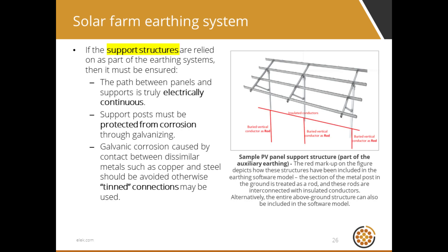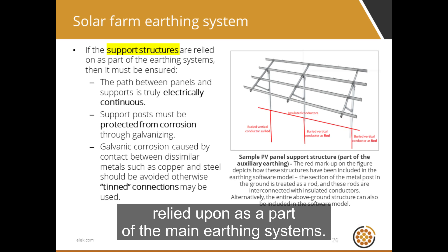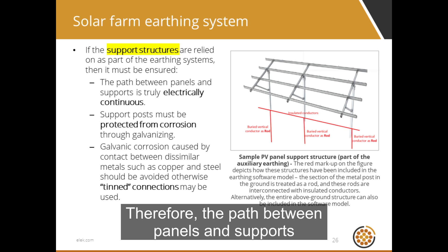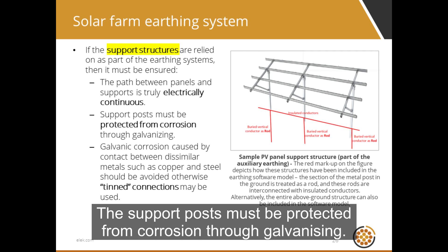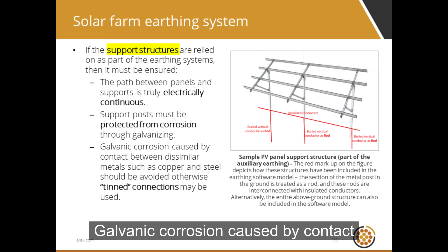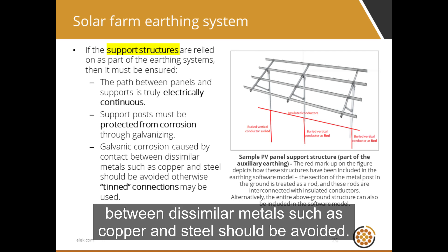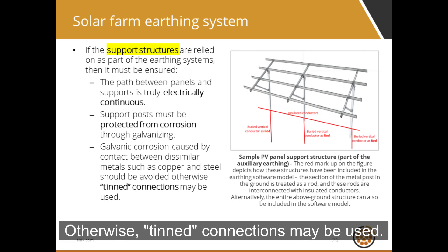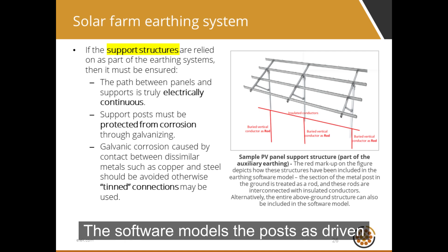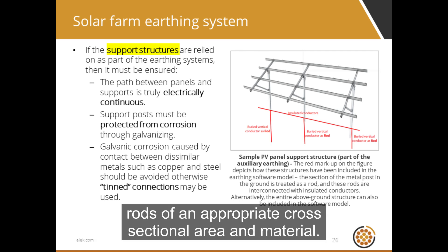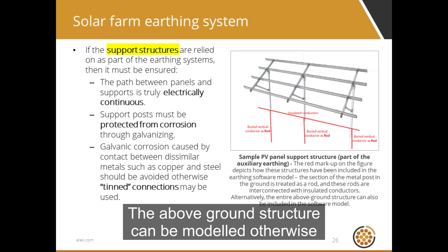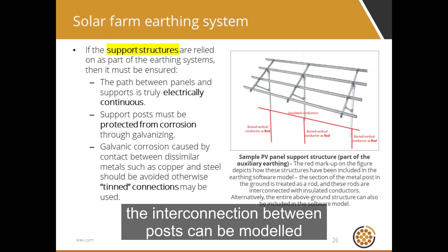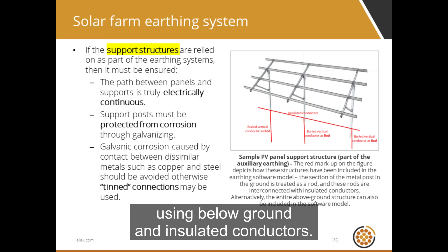The panel support structures are often relied upon as part of the main earthing systems; therefore, the path between panels and supports must be electrically continuous. The support posts must be protected from corrosion through galvanizing. Galvanic corrosion caused by contact between dissimilar metals such as copper and steel should be avoided — otherwise, tinned connections may be used. The software model models the posts as driven rods of an appropriate cross-sectional area and material. There are two ways of modeling the support structures: the above-ground structure can be modeled, or the interconnection between posts can be modeled using below-ground insulated conductors.